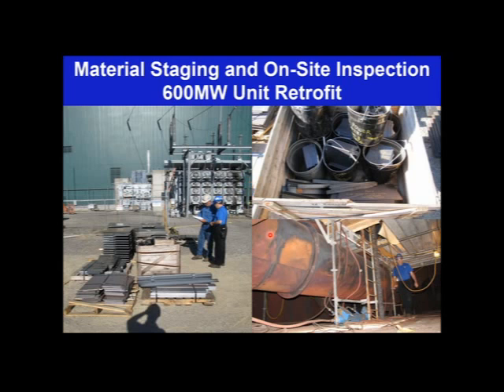This is a plant. We went through step 1, 2, and 3. We were able to identify an air binding problem in this condenser and justify stage 4. I'm going to show you the results from the phase 3 effort, and try to give you the reason for justifying this upgrade to this condenser. But this is a picture of us during stage 4. We've designed a change to the condenser. We've shipped all these parts, and during an outage, we installed a condenser retrofit.